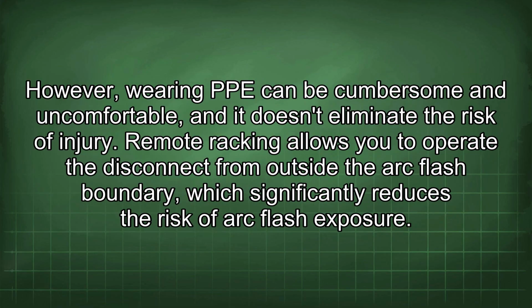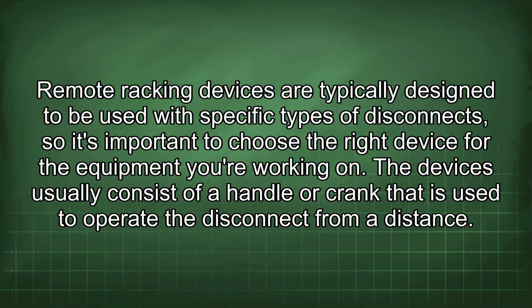However, wearing PPE can be cumbersome and uncomfortable, and it doesn't eliminate the risk of injury. Remote racking allows you to operate the disconnect from outside the arc flash boundary, which significantly reduces the risk of arc flash exposure. Remote racking devices are typically designed to be used with specific types of disconnects, so it's important to choose the right device for the equipment you're working on. The devices usually consist of a handle or crank that is used to operate the disconnect from a distance.